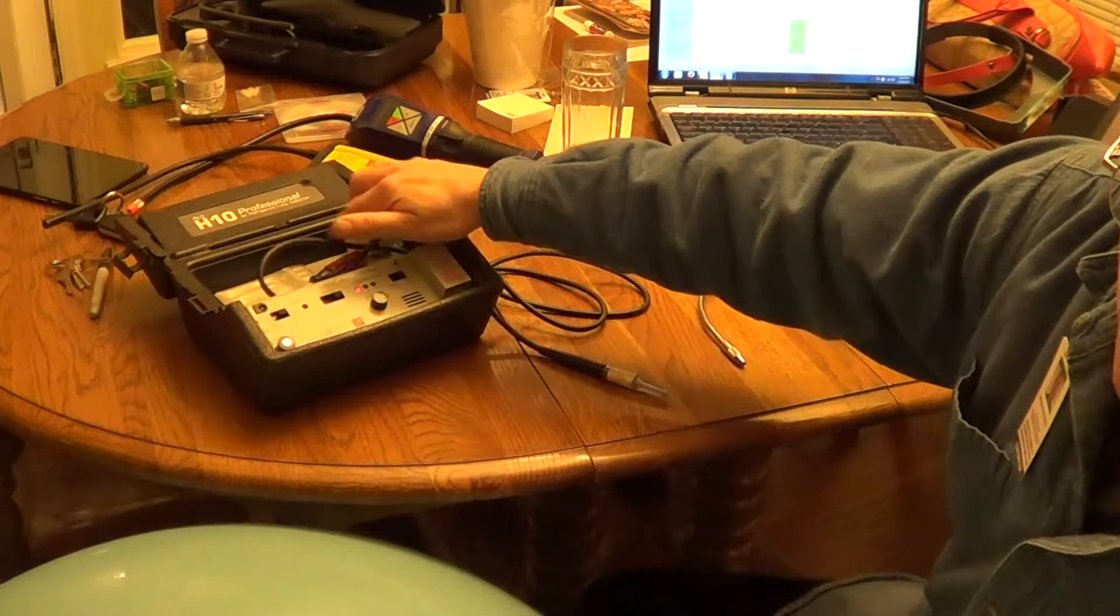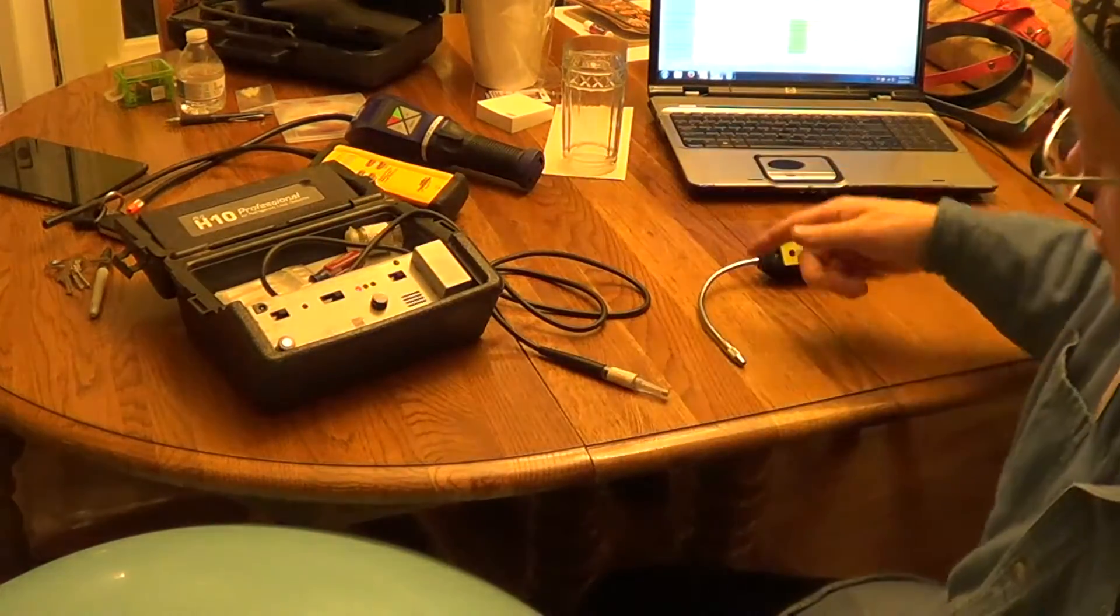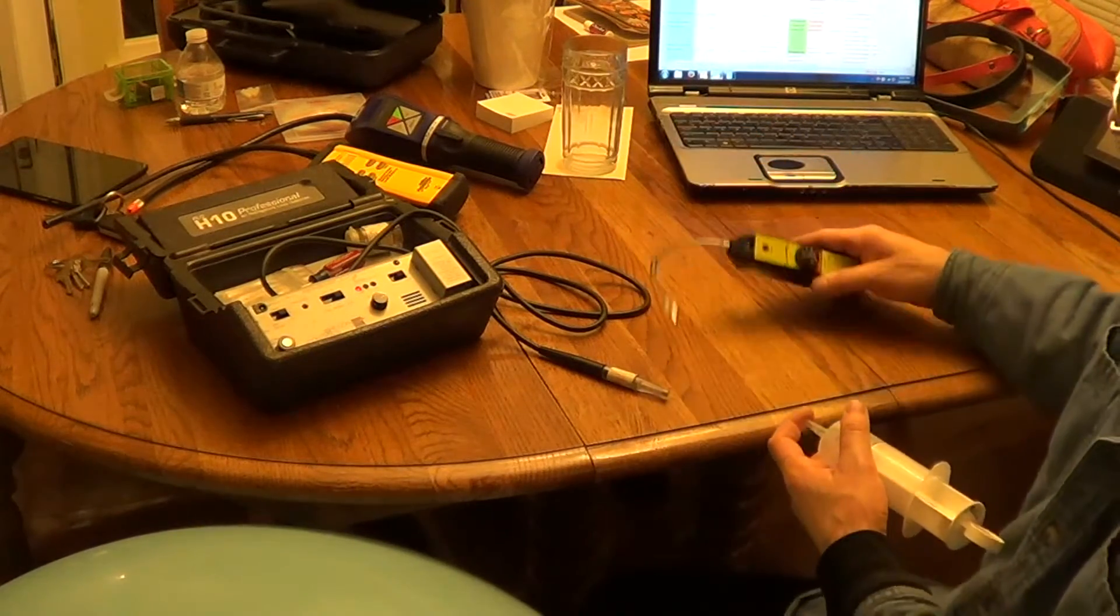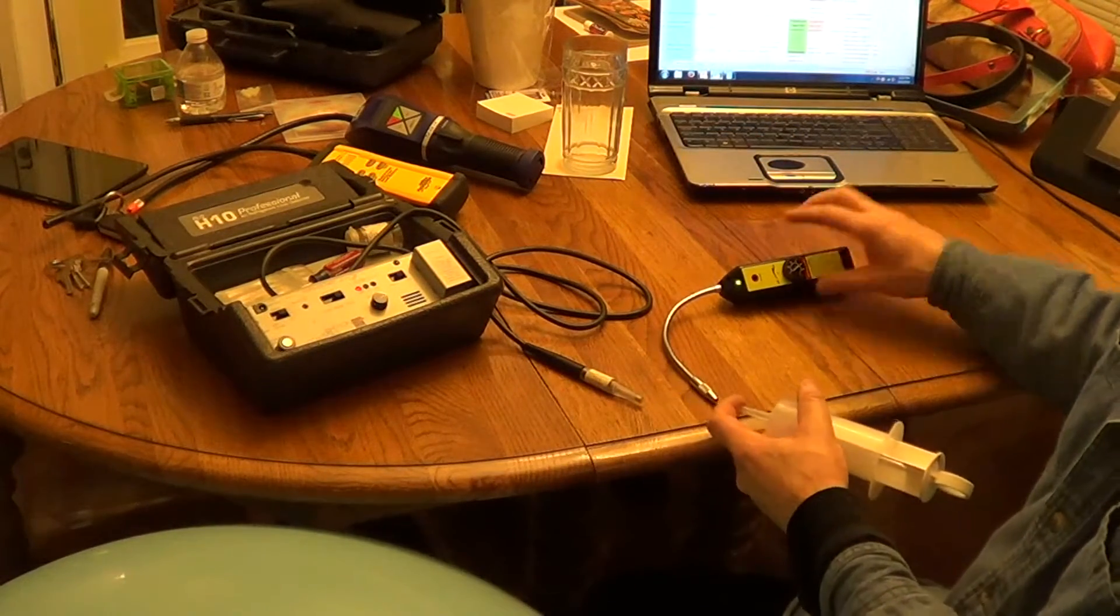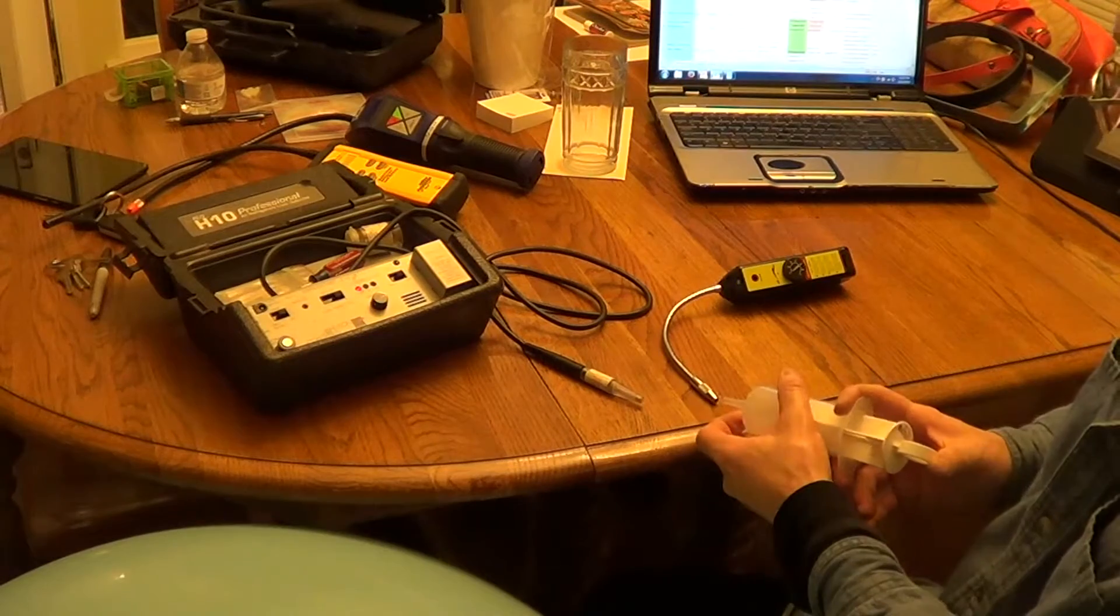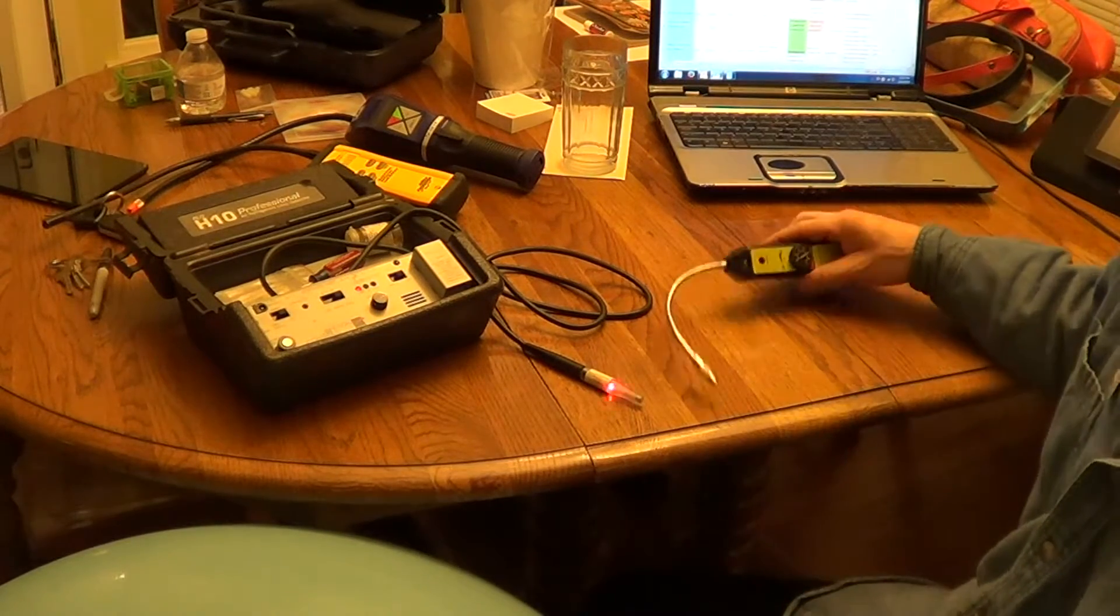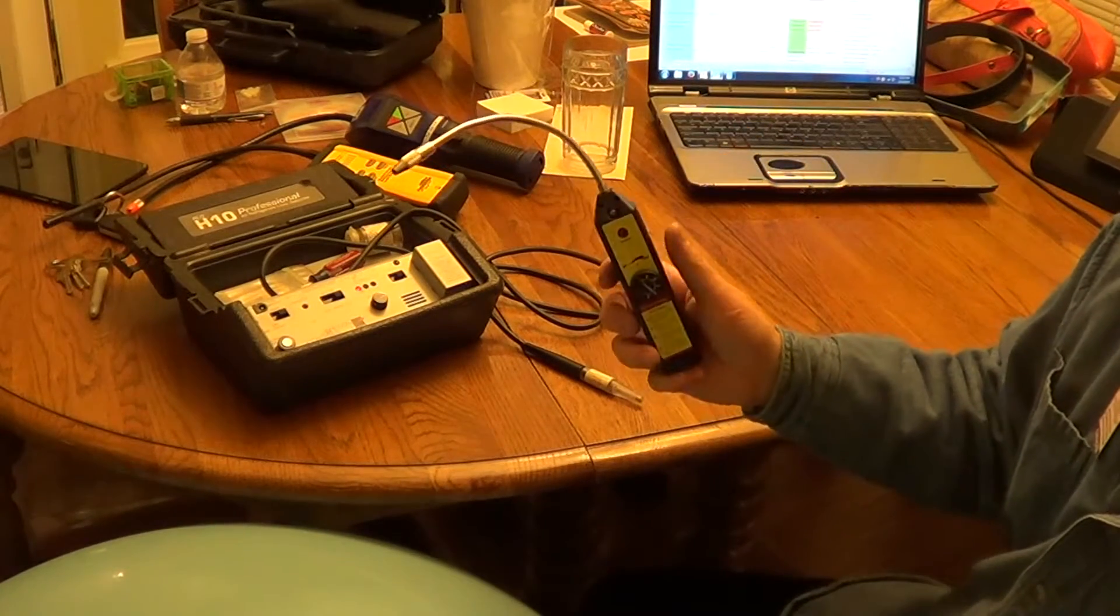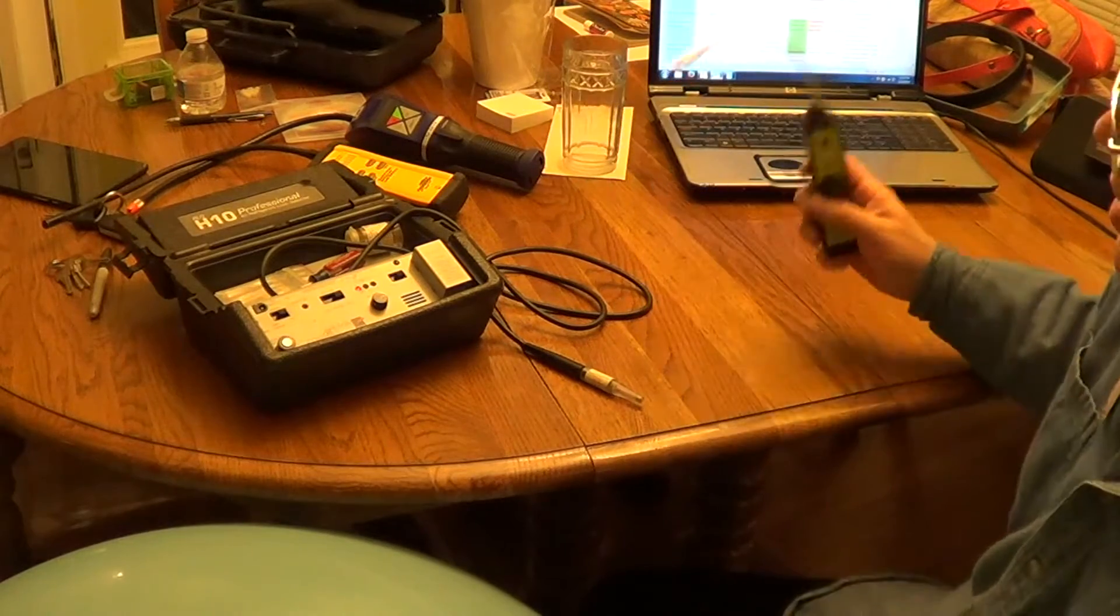The sensitivity is actually 20 parts per million. 10 parts per million R410A on my $20 Chinese leak detector. You see it easily picks it up. Actually this one picks up down to 5 parts per million.